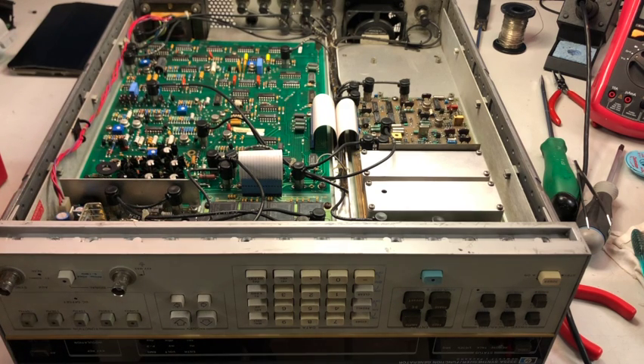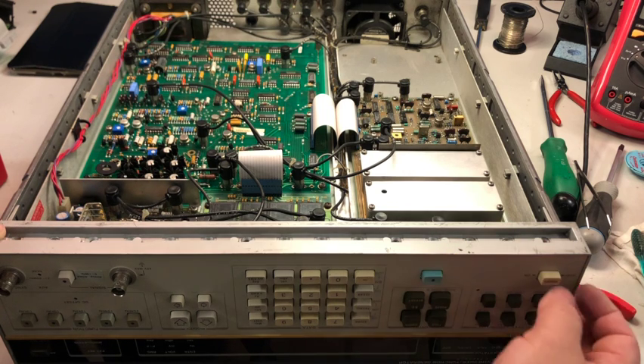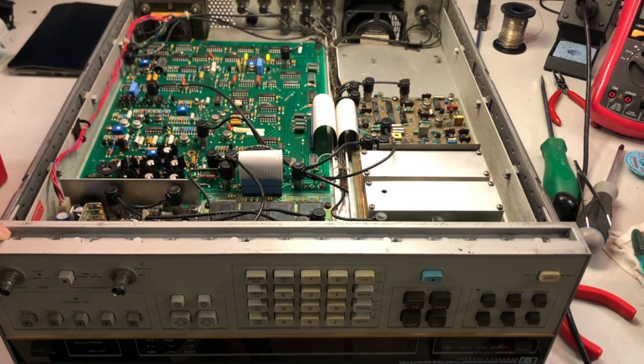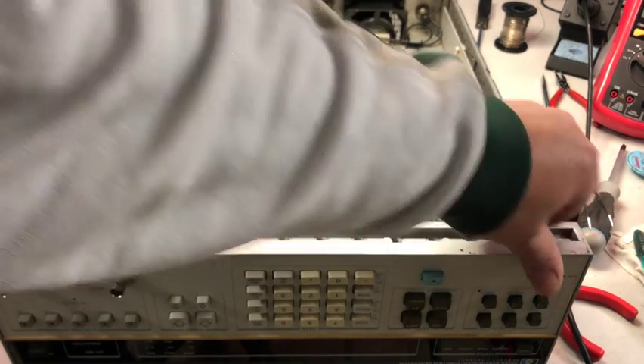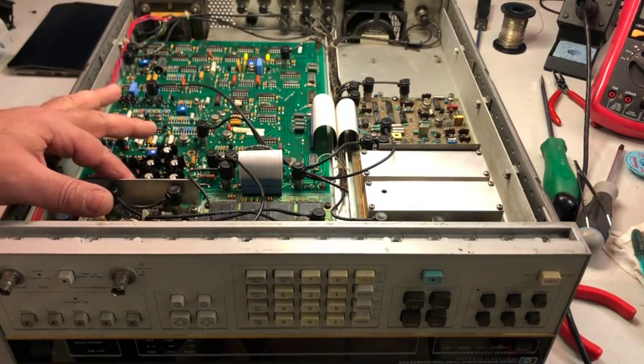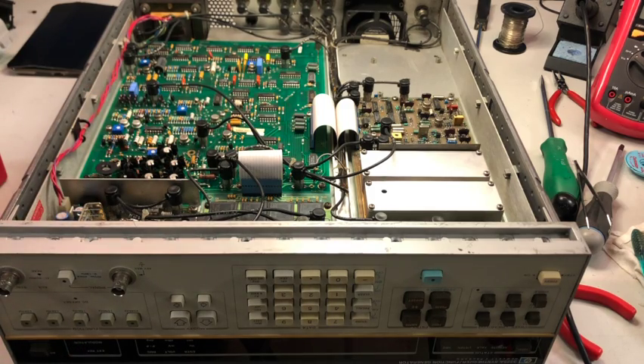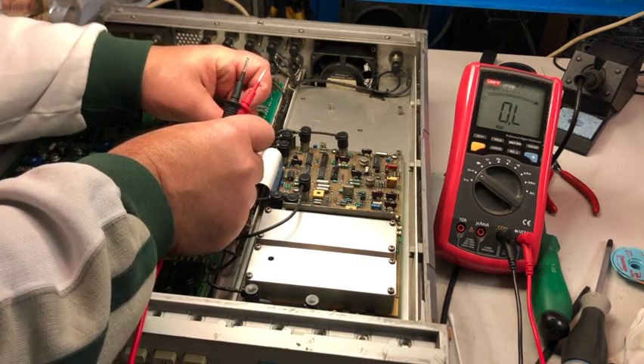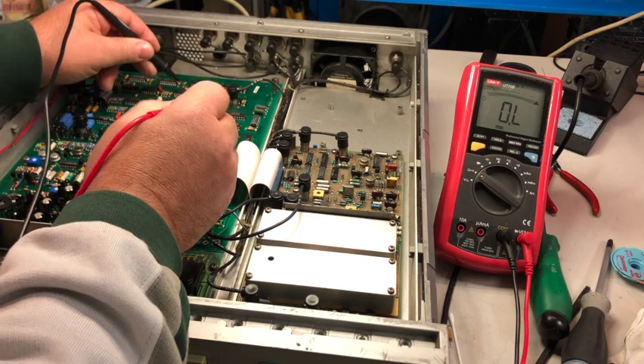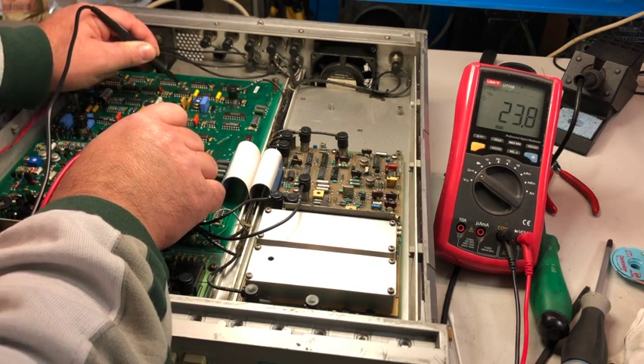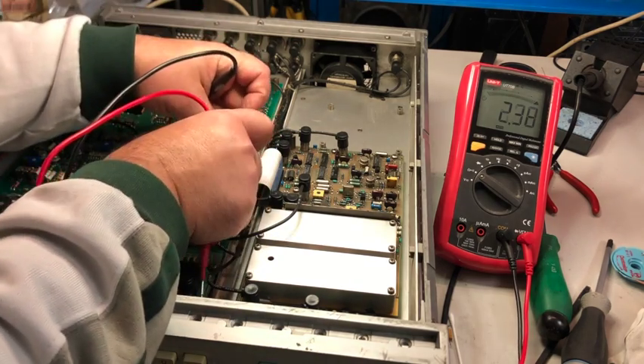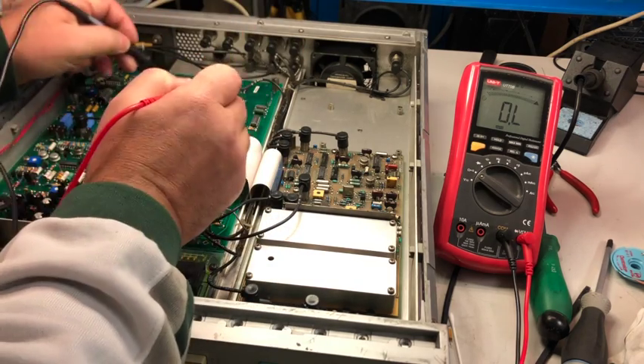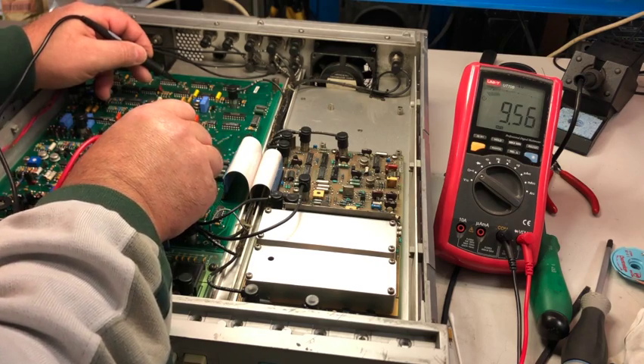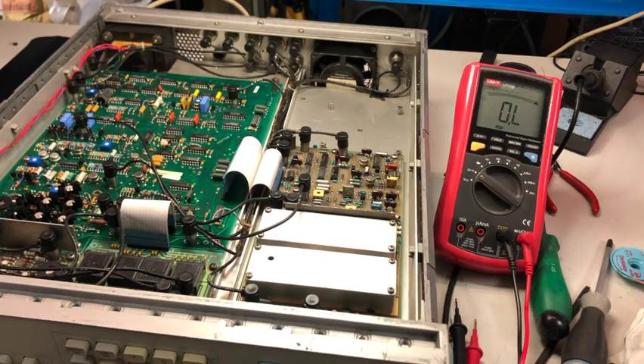The PCB is back in the instrument, so it's now time to make the test. And nope, it seems that we still have some problem. That is really weird. Let me check for some other shorts. Well, I'm actually having a similar problem as before. Look at that. If I measure this time on the plus 15 volts rail, I'm having a very low ohm reading, 23 ohms. And if I remove the ribbon cable, that goes away. So I think there is a similar problem to be checked with the schematic.